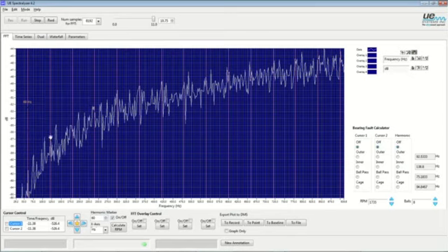I have a small 120 hertz harmonic. Then out through here, I don't get anything again till 300 hertz. There's another flat one at 360 and 420, and then pretty much nothing out here hitting on 60 hertz beyond 420. Now with corona, you're going to see all the 60 hertz harmonics at least out till 900 hertz on this frequency analyzer. Plus you will see the frequency noise here.